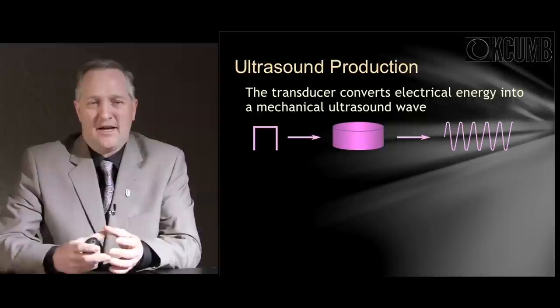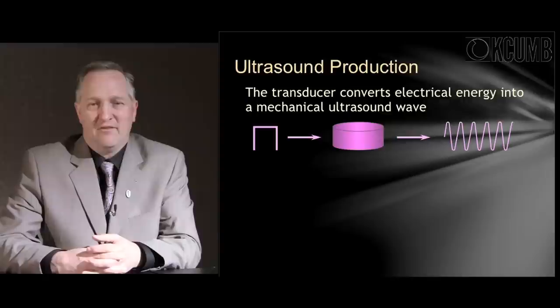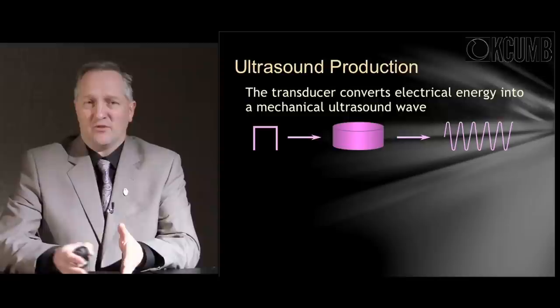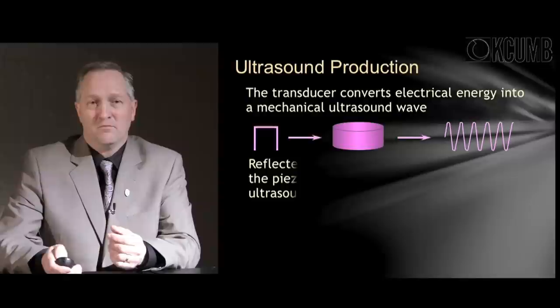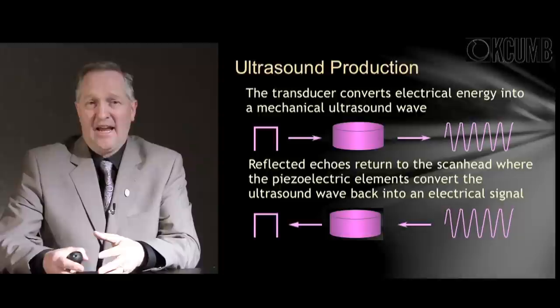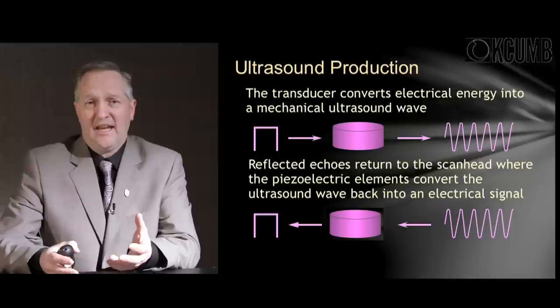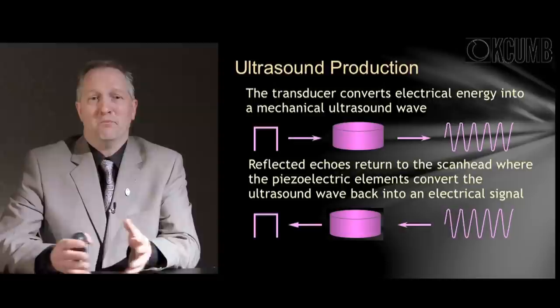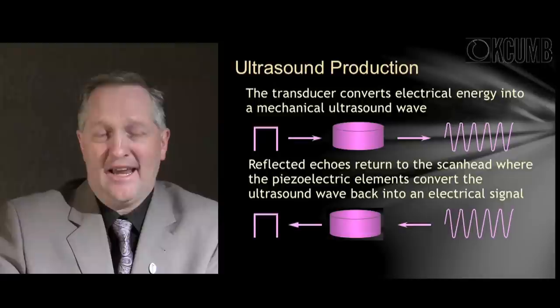Electricity is applied through the crystal, producing a longitudinal energy wave. In diagnostic ultrasound, that wave travels through the tissue — through the medium — and then it strikes something and echoes back, just like yelling in a canyon and hearing an echo bounce off the canyon wall. The wave hits whatever structure it's looking for, comes back to the crystal, and then the ultrasound machine transfers that return vibration into an electrical impulse, which is processed by the system and puts the image on the screen for interpretation.